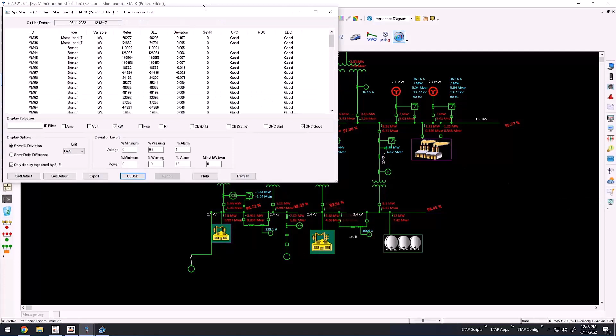Additionally, the electrical validation tool allows you to validate live measurements versus the electrical model. This helps bring to light discrepancies, for example where the model component does not reflect the as-built or operating ratings, creating a deviation in the predictive power flow. This also helps continuously keep the electrical model up to date to reflect as-operating conditions.